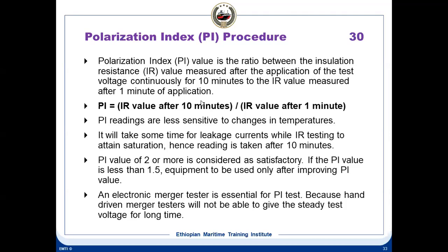It will take some time for the leakage current during IR testing to attain saturation, hence the reading is taken for 10 minutes. PI values of 2 or more are considered satisfactory. If the value you get from the 10 minute reading divided by the 1 minute reading is more than 2, it is considered satisfactory. If you get a value less than 1.5, that means you need to improve the PI value.